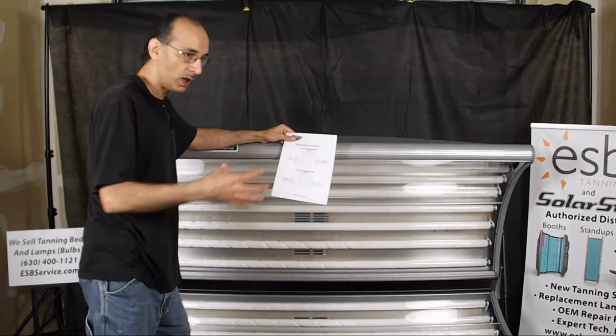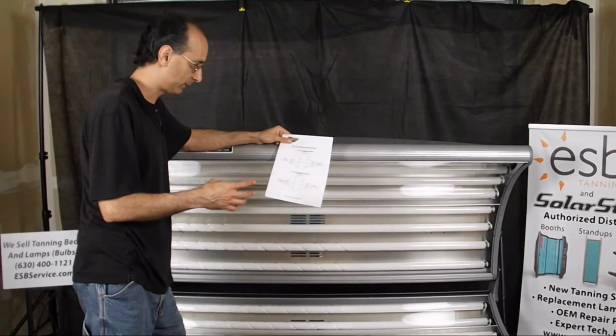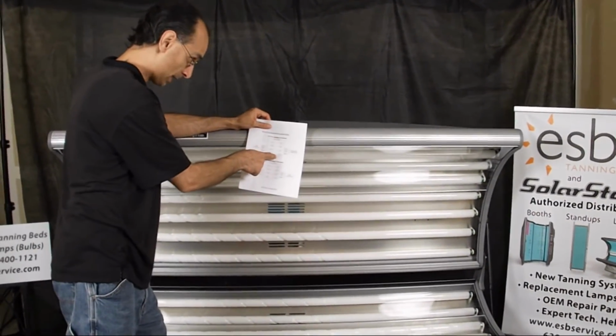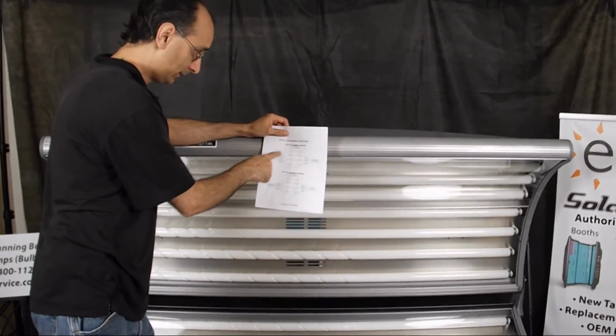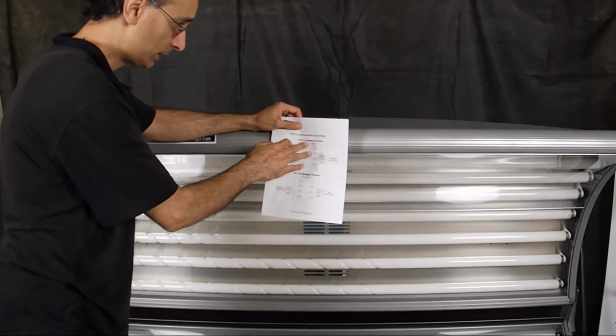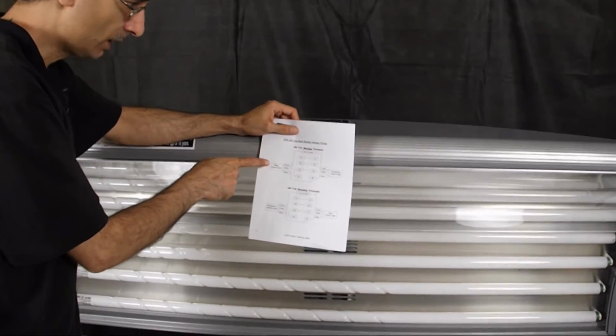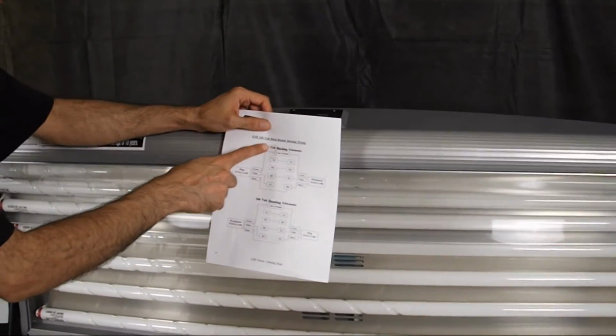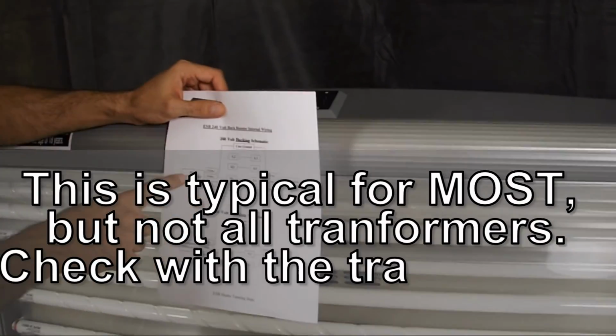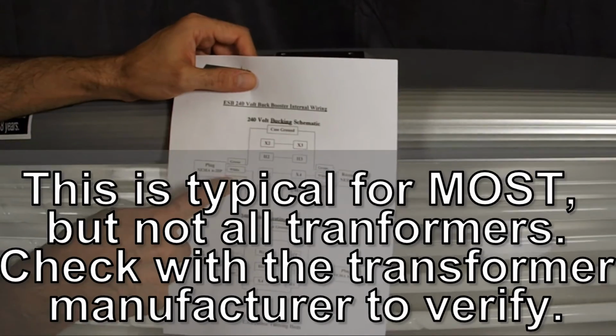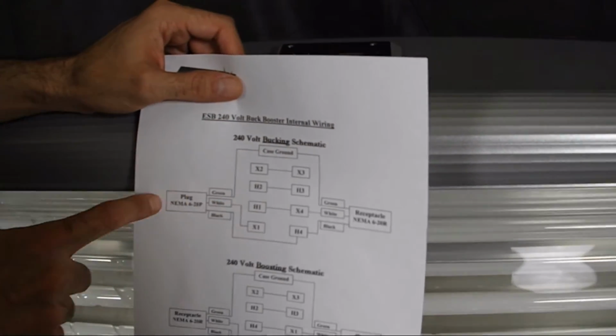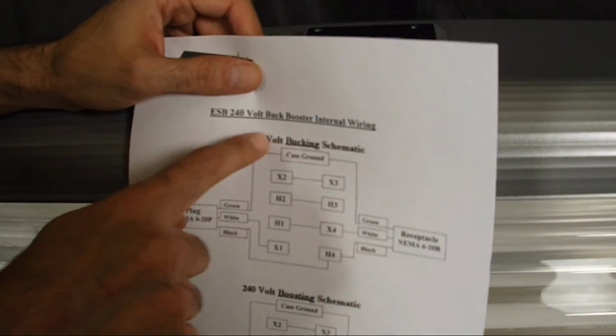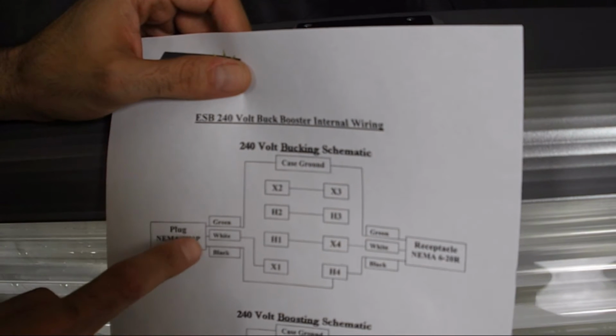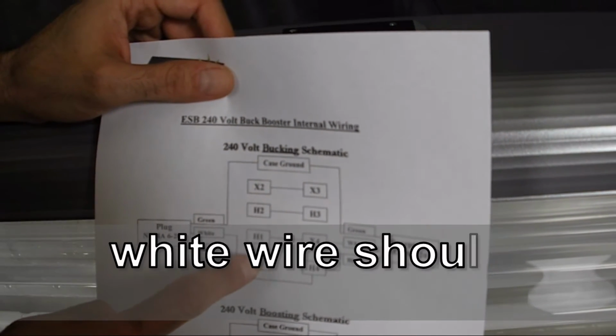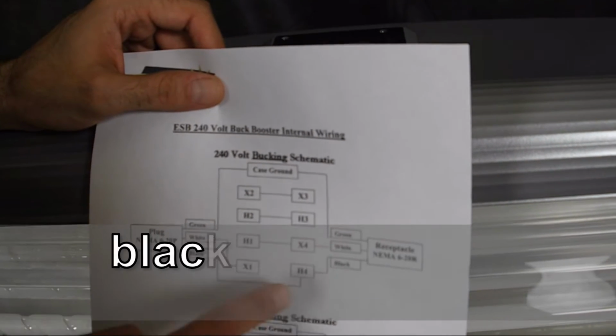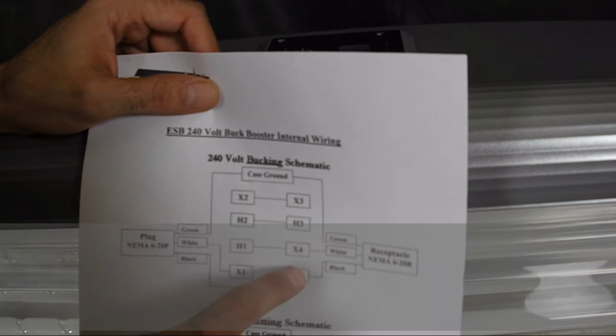Now, when you open up the buck booster case, there's going to be a bunch of wires in there. There's going to be 8 wires. Now, this is the actual wiring configuration that you will see inside the buck booster. If you are needing a bucking transformer, meaning that you're dropping the voltage down, from your plug, you're going to have a green, white, and a black. And the green is going to go to the case ground on the plug and the receptacle, as shown in the diagram here. The white from your plug is going to go to the X1 wire, and that's it. The black from your plug and from your receptacle are both going to terminate on the H4.